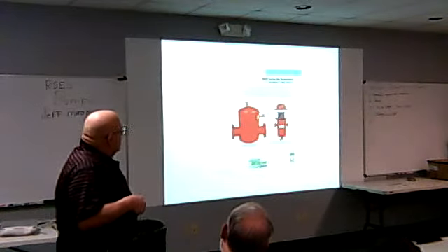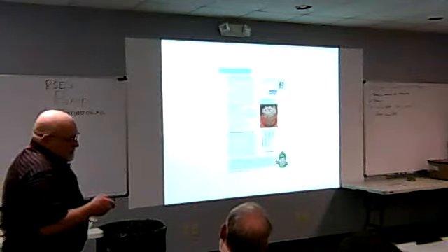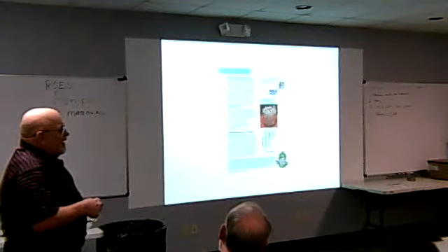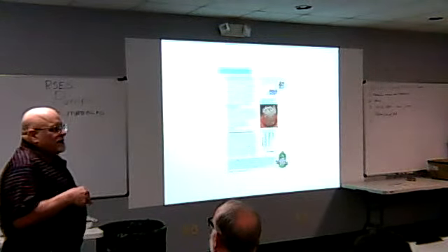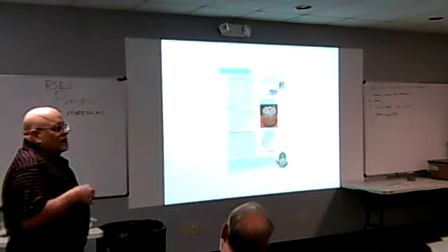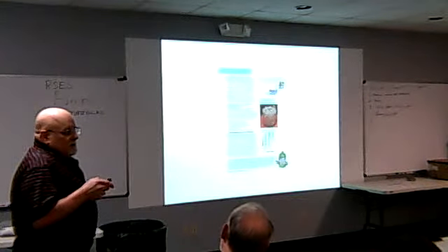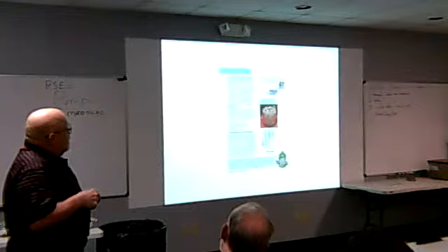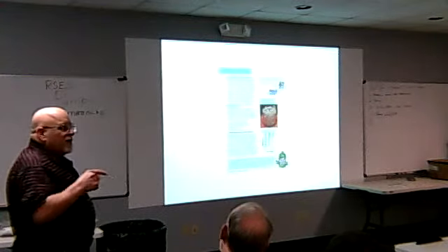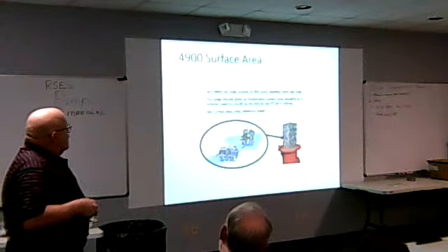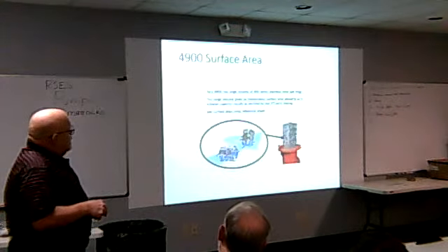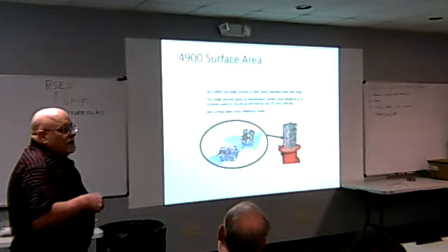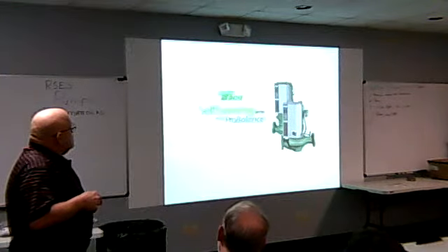There are new air separators in the world. Air separators are becoming more and more prevalent. They have different materials inside. Spirotherm uses brushes. We use these Pall rings. These new air separators will actually clean your system down to less than 20 micron. It acts as a filter, a micro condensing air separator. It'll actually take much more out compared to a regular air separator. That's that chart showing. With these Pall rings, all the fluid goes through there and it's changing directions. Very high efficiency, 125 pound ASME. We make them with a removable bladder or non-removable bladder. And you can just blow the dirt out of the bottom of them.